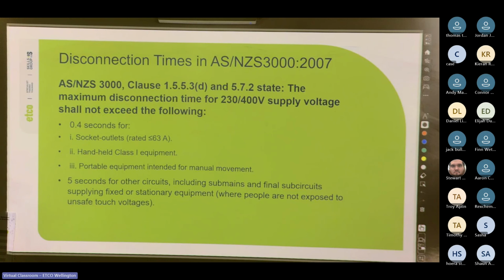So that 0.4 seconds refers to the fault protection limit. If you think about an RCBO, normally when we think about its disconnection time, we're thinking about the RCD side of things, which is 300 milliseconds at its rated current or 40 at 5 times. But because it also incorporates overcurrent or short circuit protection, it is allowed to trip at 400 milliseconds for the short circuit current. So when it's earth leakage, it's 300, but for a short circuit, it's allowed to trip in as much as 400 milliseconds.